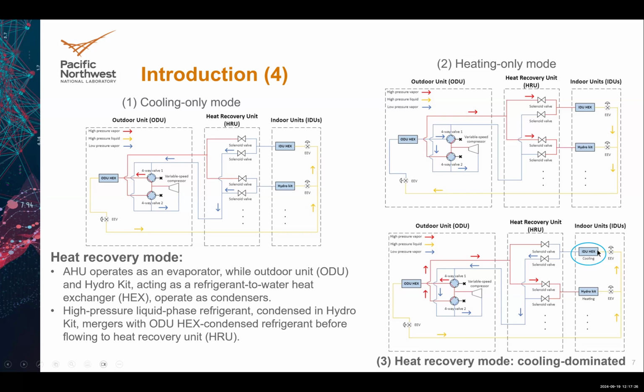For example, if your AHU's capacity is larger than your hydro kit, that means you have the cooling dominant operation for the summer season. If you need more hot water, and the hydro kit has more heat produced, that means this operation will be heating dominant mode. So it depends on the heating capacity of these two indoor terminals. For either heating or cooling, it's the same refrigerant circulation, but for different modes you have different directions.